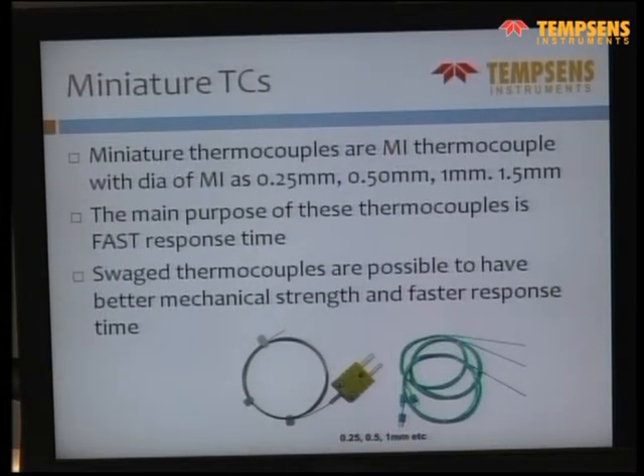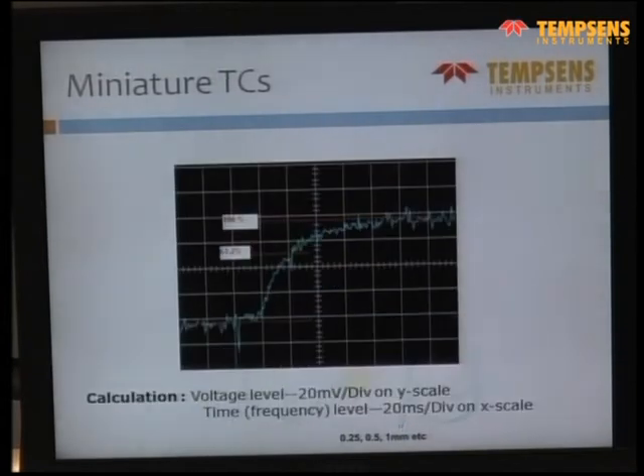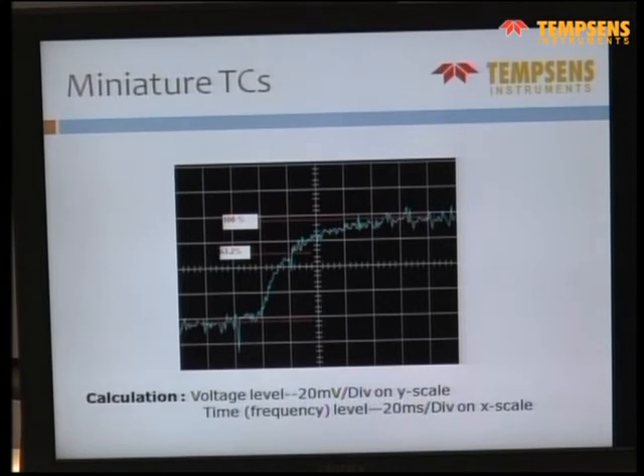Miniature sensors are available right from 0.25 mm diameter. So the wire would be only 0.04 or 0.03 mm, and you can have a response time of about 30 milliseconds with such a thing. Also, swage thermocouple means the tip would be narrowed from the bottom so that it gives better response time. So these kinds of things can also be available.